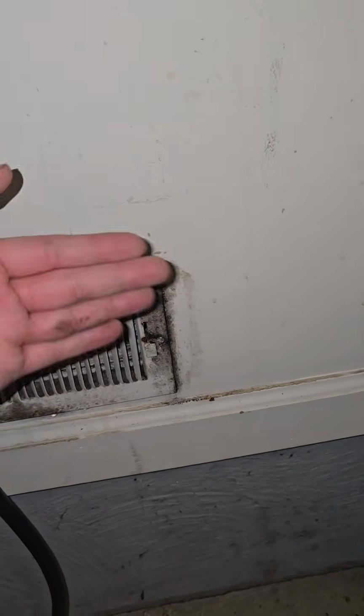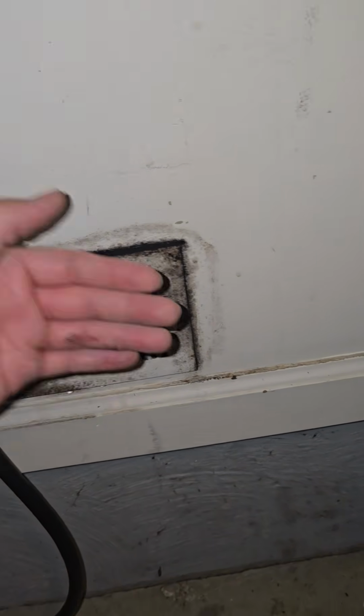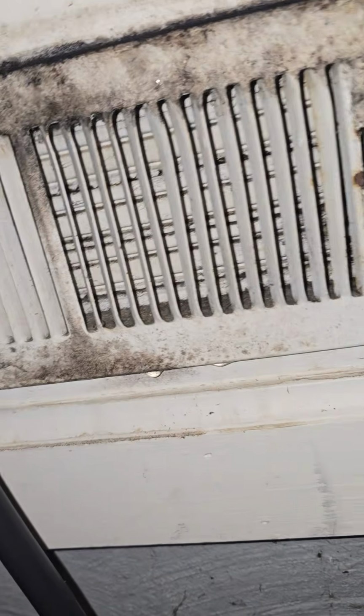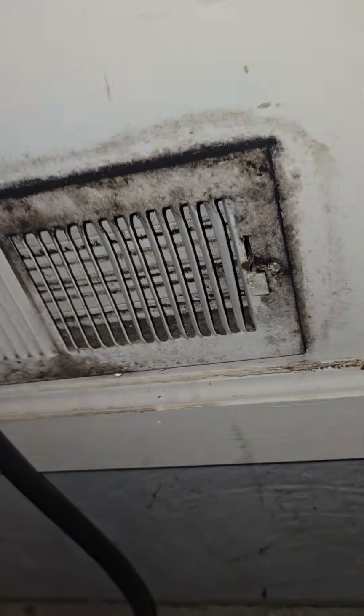Now, condensation occurs at what we call the dew point. That's the point that is determined by the temperature of the air and the humidity of the air. And there's a formula for that, or a meter will tell you that. It's not really relevant, though. Anytime you have a big extreme in differences of temperatures, like a really cold vent in a warm garage, you're probably going to get some condensation. And yes, this vent is closed, and that's probably contributing to it, but even if it was open, this probably would still be happening.